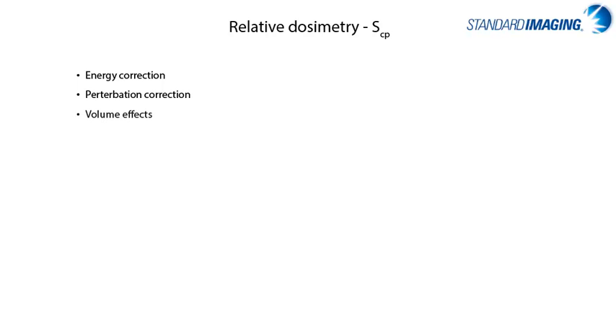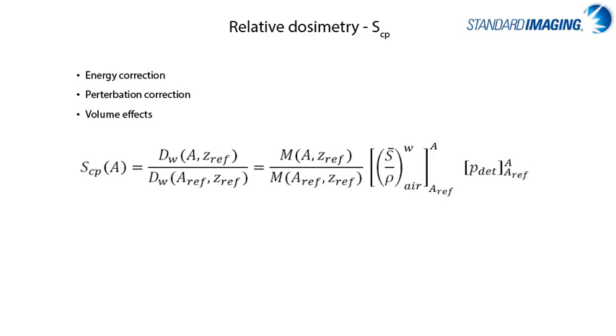Considering output factor measurements, it is important to select a detector that is appropriate as to minimize the energy correction, perturbation, and volume effects, or at least have a dosimeter with known effects which are often based on published peer-reviewed studies on the topic. This generalized equation shows the parameters that go into determining output factors when considering the ratioed measurements from the standard field, the stopping powers, and any perturbation effects.